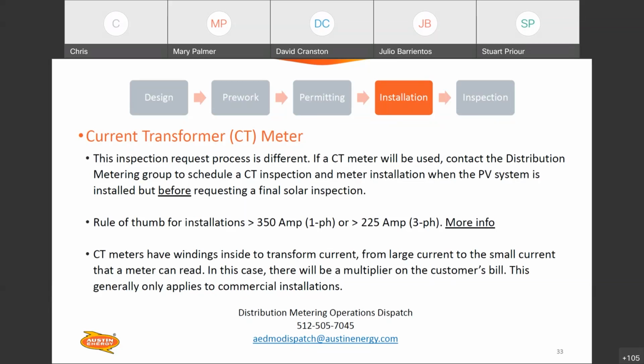So just keep in mind that if it's not the regular self-contained meter can that you're used to getting with the bypass handle at the supply house, then you're probably going to have a separate inspection process. The rule of thumb for that is anything that's single phase over 350 amps or 3-phase that's 225, more than likely you're going to have a CT meter. And that's the contact information down there below for metering operations. You'll get in contact with them to request that inspection. All right, next.